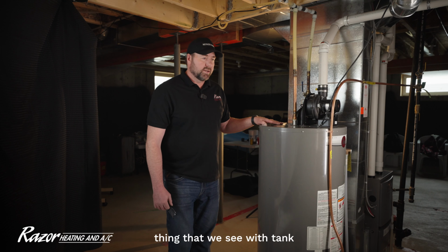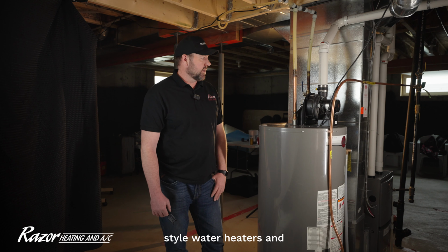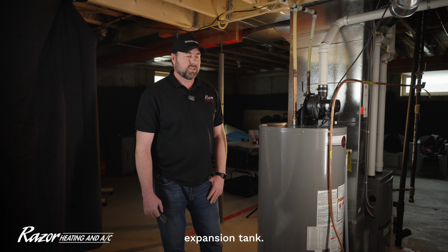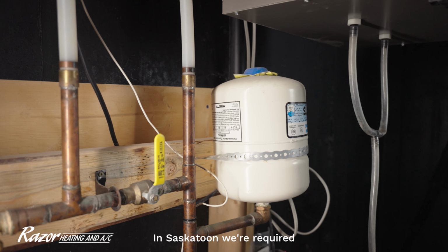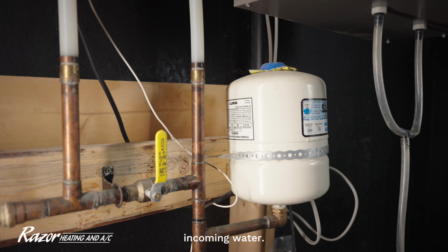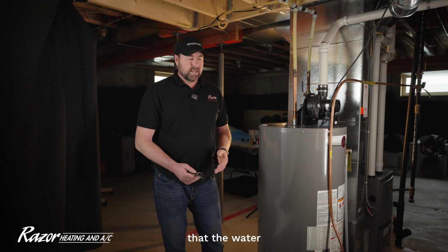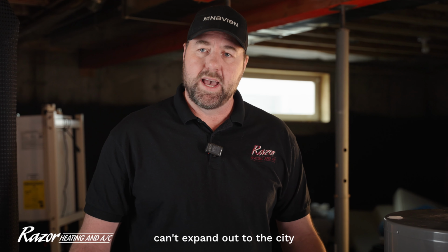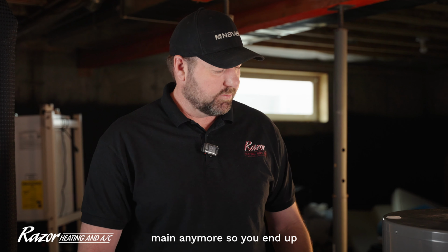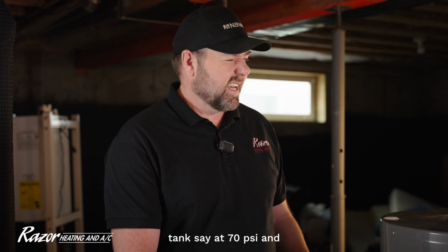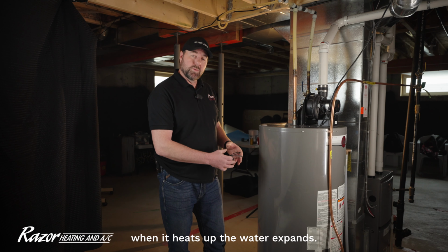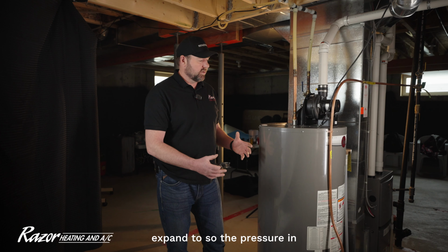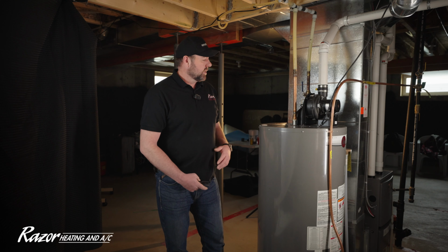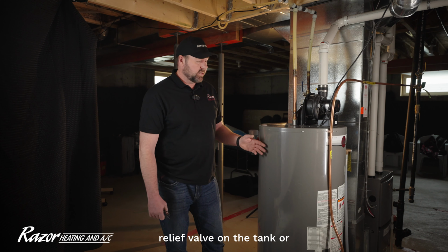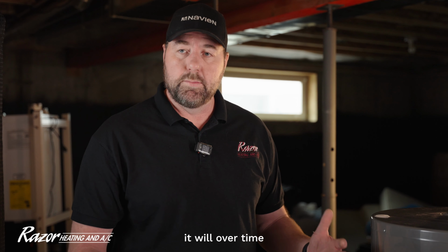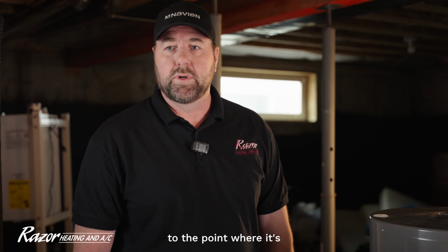Probably the biggest thing that we see with tank style water heaters and premature failure is the expansion tank. In Saskatoon, we're required to put a check valve on the incoming water. When you do that, the water can't expand out to the city main anymore. So you end up with a cold water tank, say at 70 psi, and when it heats up, the water expands. It's got nowhere to expand to, so the pressure in the tank goes up, and it will either blow the relief valve on the tank, or it will, over time, distort the tank to the point where it's leaking.